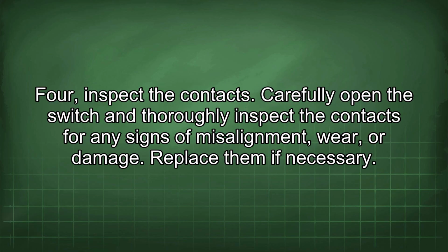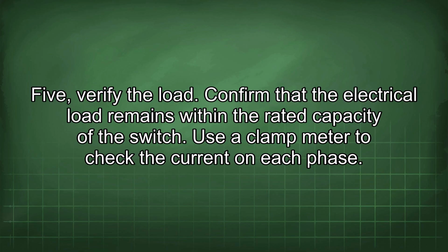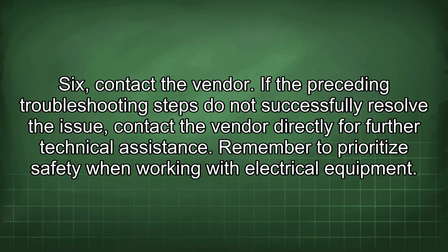4. Inspect the contacts. Carefully open the switch and thoroughly inspect the contacts for any signs of misalignment, wear, or damage. Replace them if necessary. 5. Verify the load. Confirm that the electrical load remains within the rated capacity of the switch. Use a clamp meter to check the current on each phase. 6. Contact the vendor. If the preceding troubleshooting steps do not successfully resolve the issue, contact the vendor directly for further technical assistance. Remember to prioritize safety when working with electrical equipment.